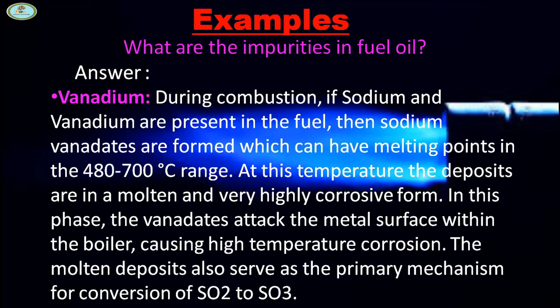In this phase, the vanadium attacks the metal surface within the boiler, causing high temperature corrosion. The molten deposits also serve as the primary mechanism for conversion of SO2 to SO3.